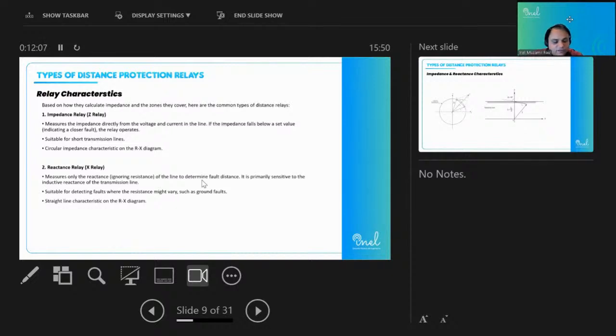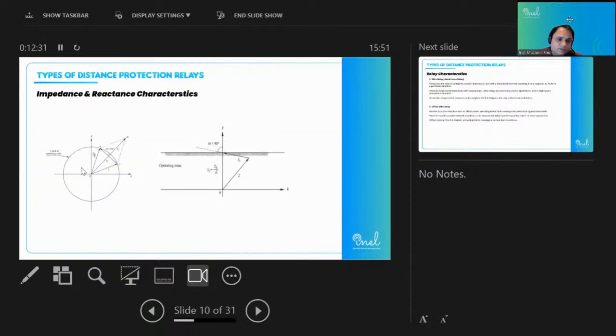So first of all, there is a very simple characteristic which any relay will have. This is the impedance relay, where we have the RX plane. We put R on the x-axis and reactance on the y-axis, and there is a circle whose center is like this one. This is the impedance characteristic of the relay. So this is the R plane, this is the X plane, and this circle is the characteristic of the relay. Now, from this point to this point, this is the resistance of the transmission line, and on the y-axis, this is the reactance of the transmission line. Like we have R plus jX.